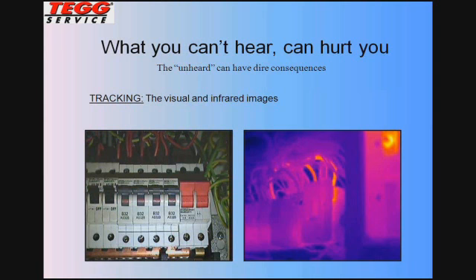Interestingly, and as I noted before, you do not see that on the infrared. You see load-related heat here on the right side with the infrared images, but there's nothing to suggest that something may be occurring inside this device. So it's another example of how ultrasound has definitely helped identify something far more early than infrared could, because we don't have excessive current flow resulting from the tracking to the point where the infrared camera could see it.